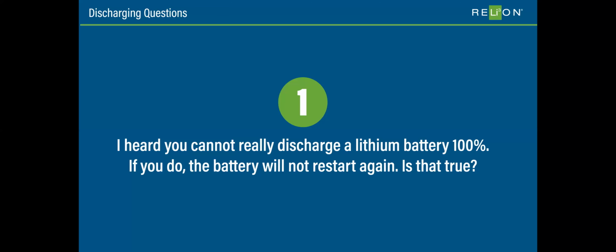So it's kind of three grades of answers - hopefully that gives you a good picture of the implications of discharging a battery to 100%. A lot of equipment has settings for a low battery voltage cutout - LBCO, LVCO, LVD. It's good practice to set those parameters, and contact our tech support if you need help, so your battery disconnects at 90% or 95% discharged, avoiding the nuisance of a BMS disconnect.